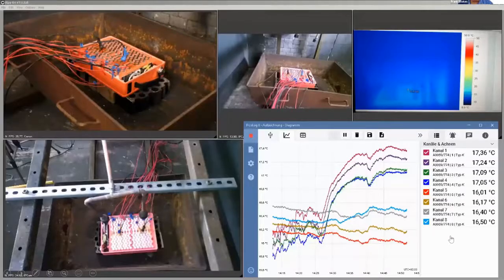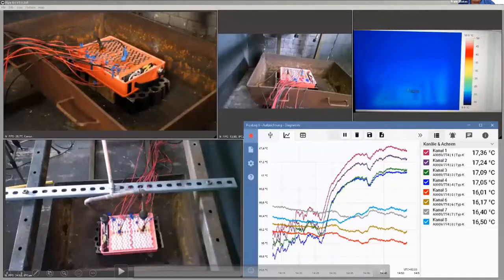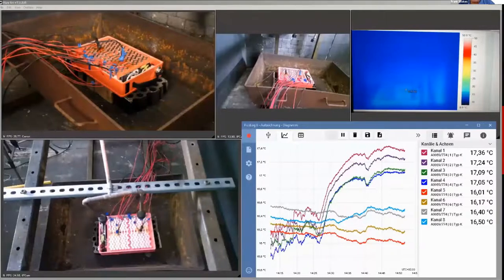This is a pretty long video, so I'm going to speed through it. Just want to point out a couple things. You have multiple images on screen - the batteries are tied with thermocouples, and there are two nozzles fixed above the battery connected to an extinguisher. The top right is a thermal imager, and the bottom right is the graph measuring the thermocouple readings. So I'll get this started.